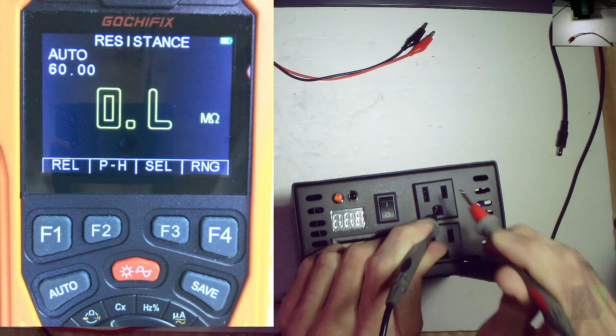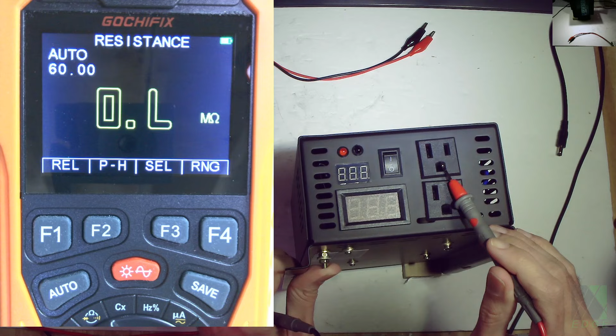Just to be clear, in many cases on many inverters, this ground terminal is literally floating—it's not connected to anything. But you still need to check resistance between all these terminals, because if there happens to be a short circuit or a failure, you need to know that. There are some inverters I've never actually seen myself, but they must exist, that present voltage between ground and these 2 terminals—so you'd get voltage from here to here and voltage from here to here. I've never personally seen one, but I've heard they do exist, just so you're aware.